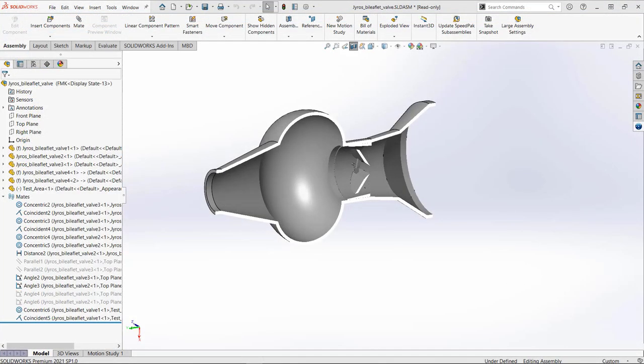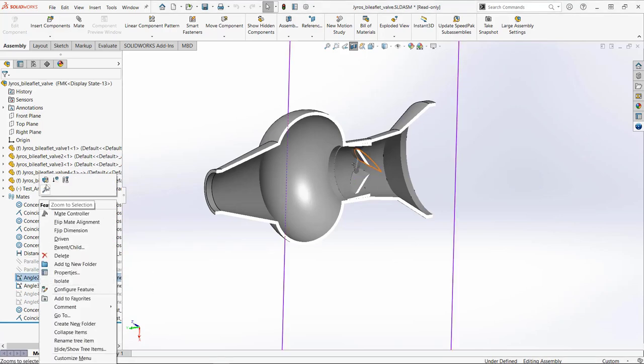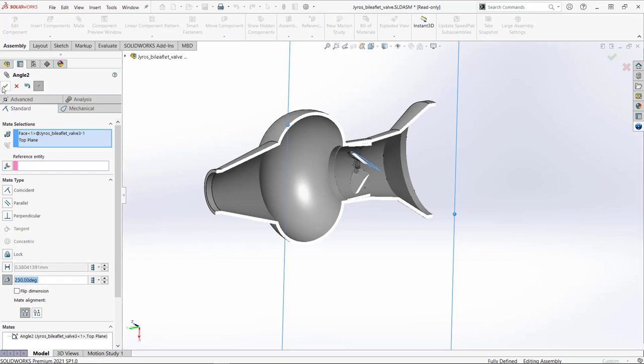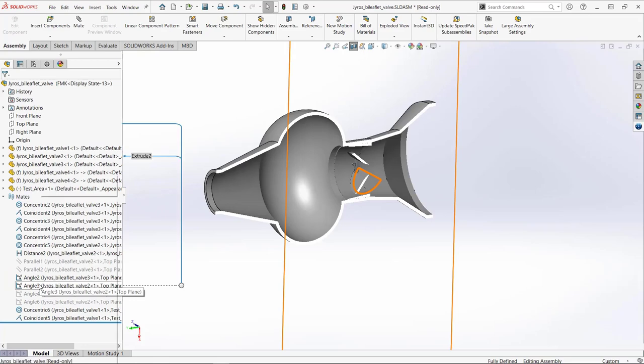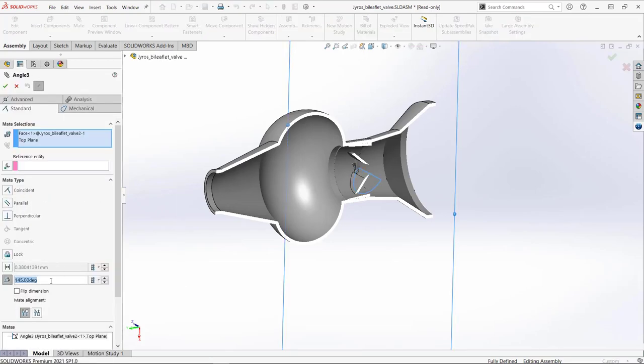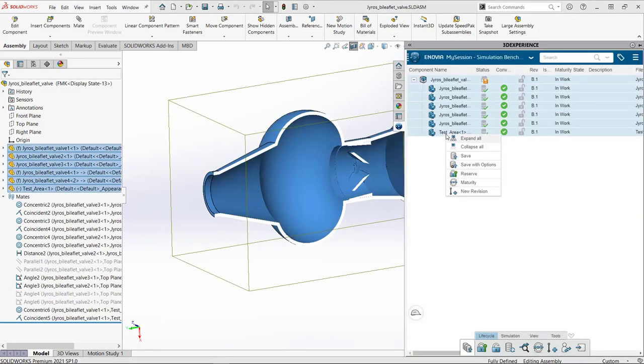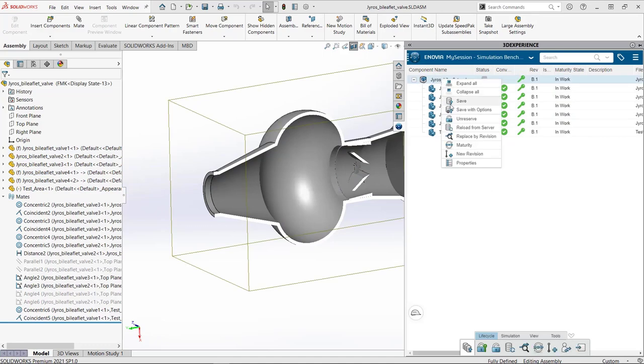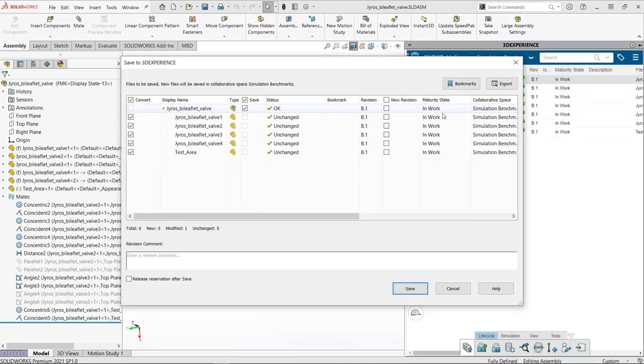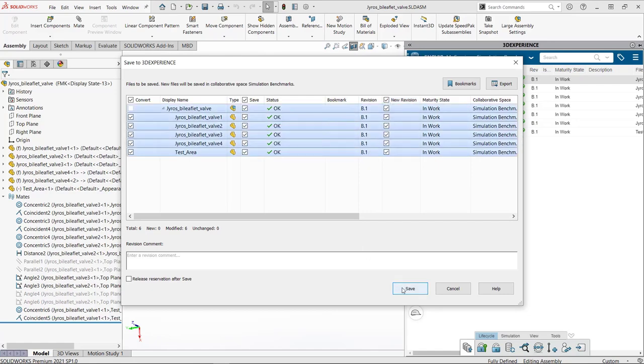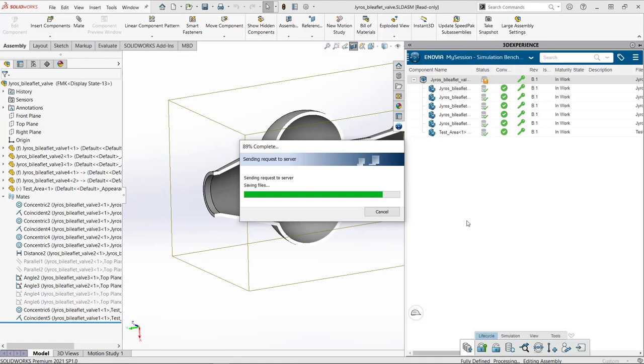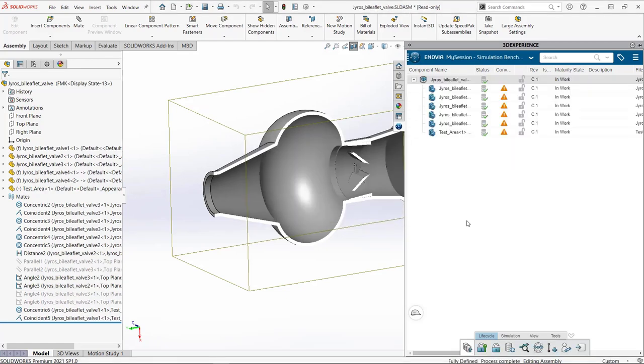I'd like to show how design changes can be driven directly from SOLIDWORKS — the biggest benefit of using this 3D Experience technology. Here I have the heart valve design in SOLIDWORKS, and I'm going to modify the mates of the leaflets to reposition their angle. Once I've modified both mates, I use the 3D Experience connector to push these design changes onto the simulation environment. I then save the modified design and increase the version or revision number, maintaining a history of all designs and their respective simulation results.